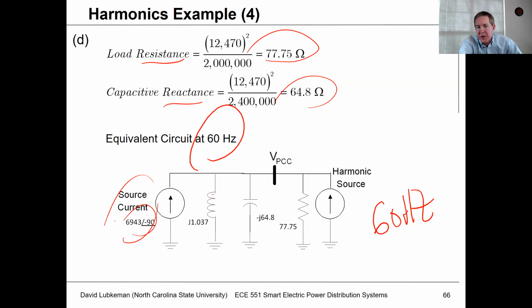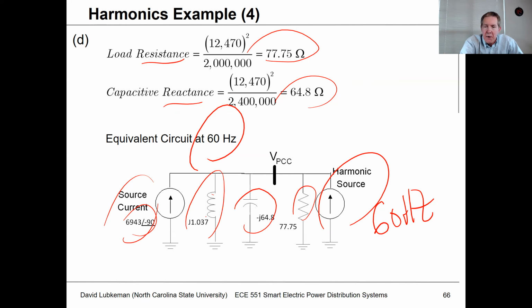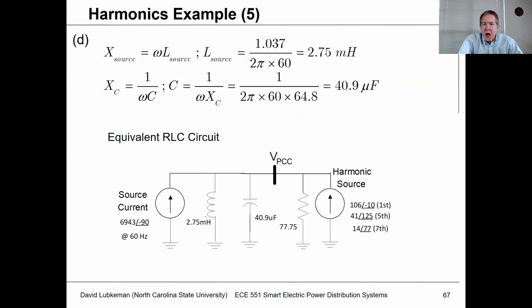Basically, this is going to be the short circuit current. I've got my equivalent load resistance, my equivalent capacitor reactance, and my system series inductance. But this is the equivalent system right here at 60 hertz. Now, the problem we run into is I've got to look at this response not only at 60 hertz, but also at the 5th and 7th harmonic, at other frequencies, 300 hertz and 420. So in order to do that, I've got to take into account that the reactance is going to change by omega times L, and the capacitive reactance by 1 over omega C. So then I can calculate an equivalent inductance for the source and an equivalent capacitance for the capacitor bank. I get a source inductance of 2.75 millihenries and an equivalent capacitor value of 40.9 microfarads.